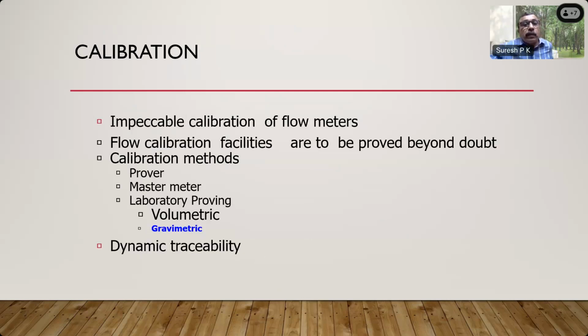Then calibration of flow meters is slightly different from calibration of other instruments, because in this case you are trying to measure something which is moving. So when the moving fluid passes through the flow meter and verification system, it has to be measured. At every flow rate you check 2 readings, or at every flow rate you check 5 readings. That depends on your calibration method and calibration requirement. There are many methods. Prover calibration is there, master meter calibration is there, laboratory proving is there. Laboratory proving itself, you can do volumetric or gravimetric.